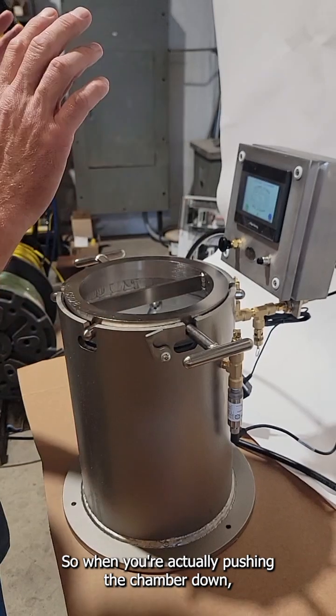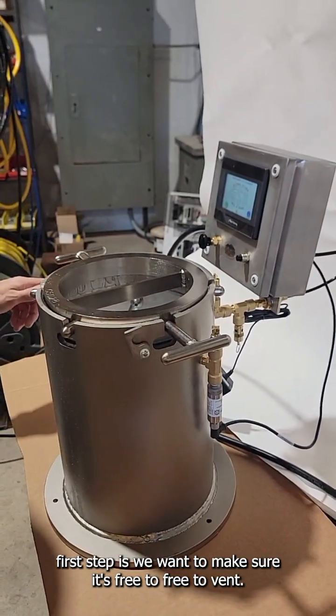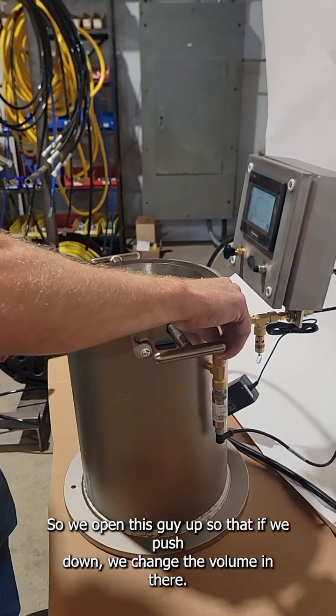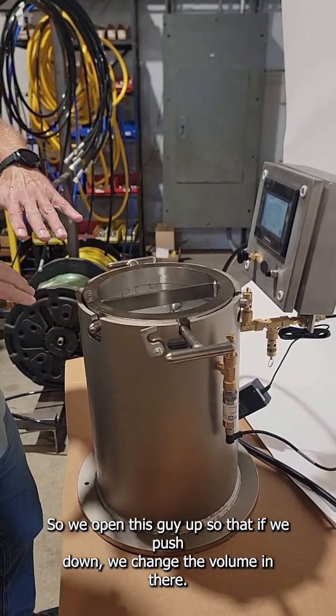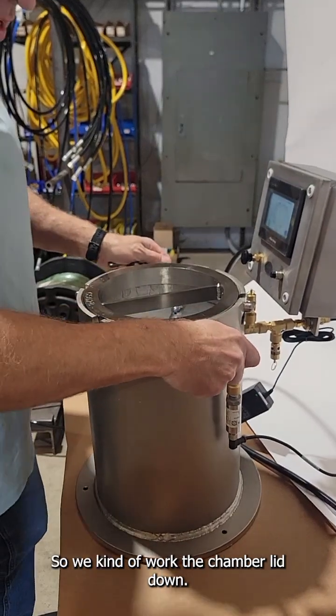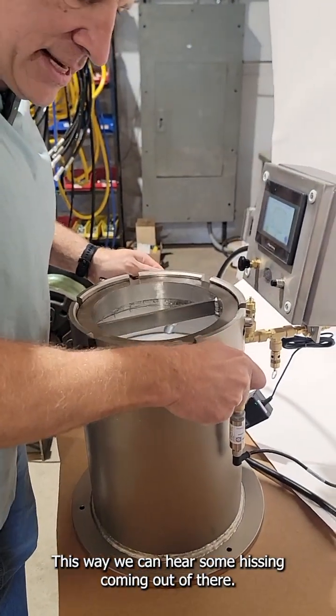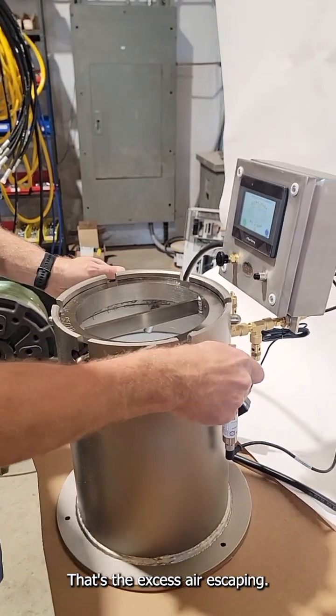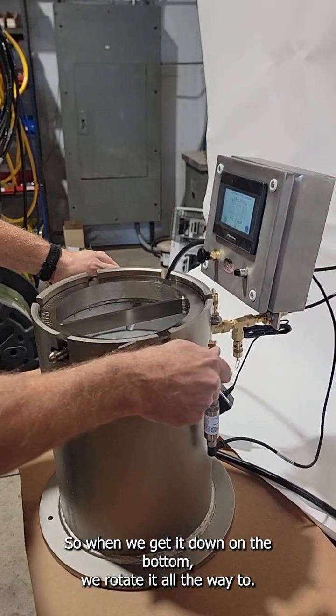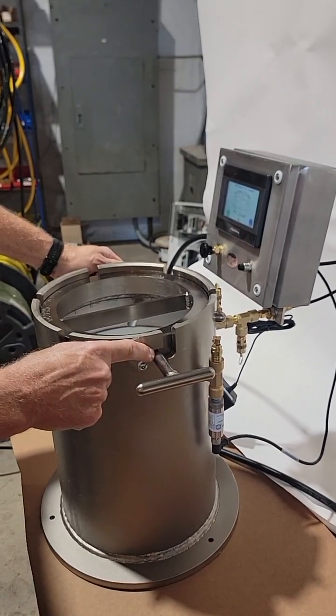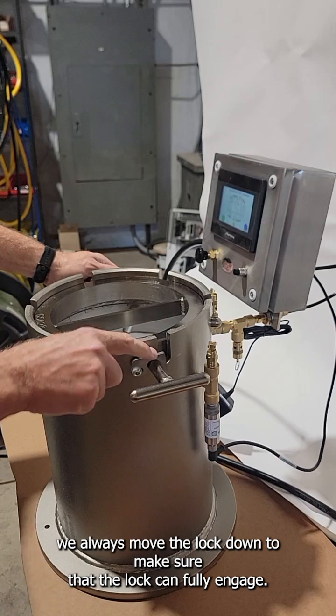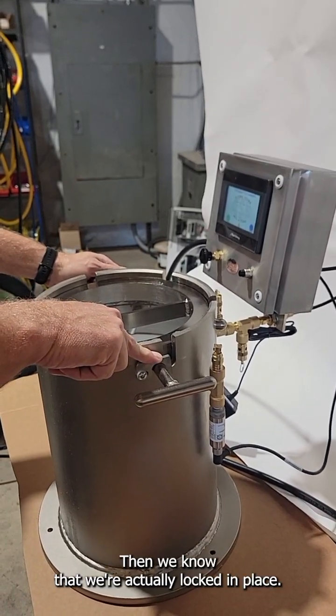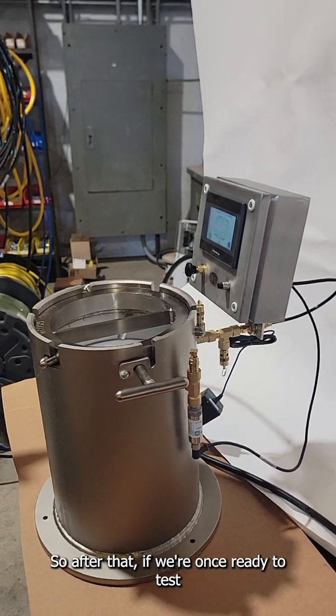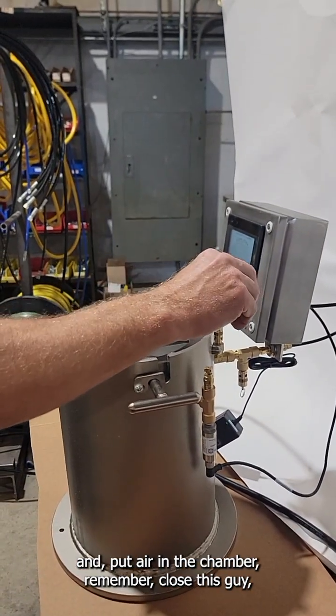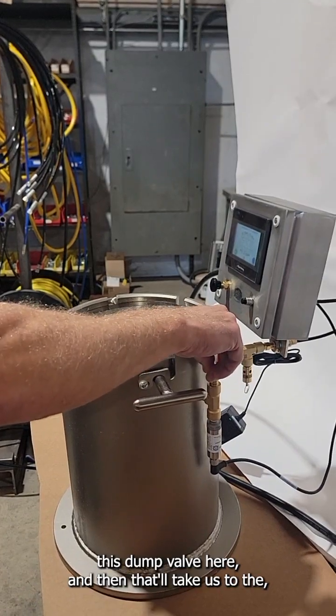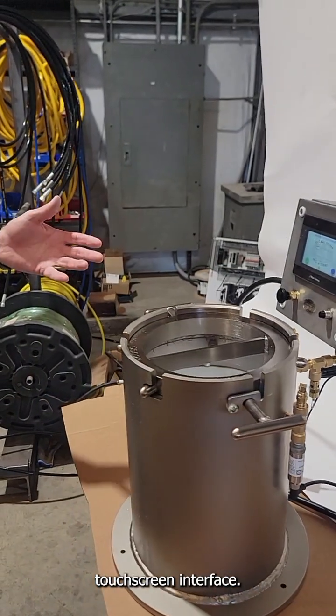It's pretty snug. So when you're pushing the chamber down, the first step is we want to make sure it's free to vent. So we open this up so that as we push down, we change the volume in there. We need to allow that air someplace to go. So we work the chamber lid down this way. We can hear some hissing coming out of there. That's the excess air escaping. When we get it down on the bottom, we rotate it all the way until we get full lug engagement here. To verify that, we always move the lock down to make sure that the lock can fully engage. Then we know that we're locked in place. After that, once we're ready to test and put air in the chamber, remember to close this dump valve here, and then that'll take us to the touchscreen interface.